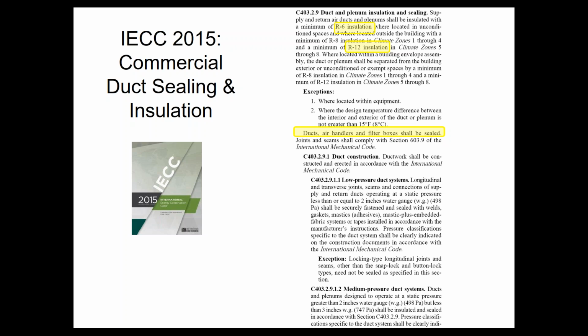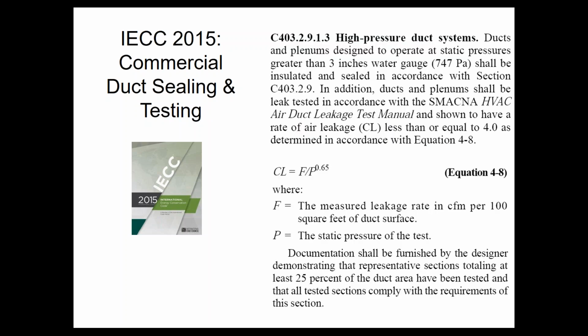Additionally, the ductwork breaks into 3 categories: low pressure, which is 2 inches and under, medium pressure, 2 to 3 inches, and high pressure, 3 inches and above. And the code then dives in and specifically tells you how you have to seal those. The one of interest right now is high pressure. If you have a high pressure system, which is 3 inches of design duct static pressure or higher, you not only have to do the duct sealing like you do on all systems, you have to do a duct leakage test as well.